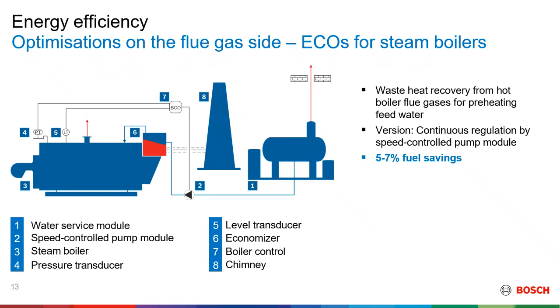So just by collecting heat from the flue gas, you've already reduced the temperature gradient between the water that is coming in and the steam that is leaving the boiler. From your normal, let's say, 85 to 90 for partial deaeration, you've actually pushed it to 130. Therefore saving you around 5 to 7% on fuel.